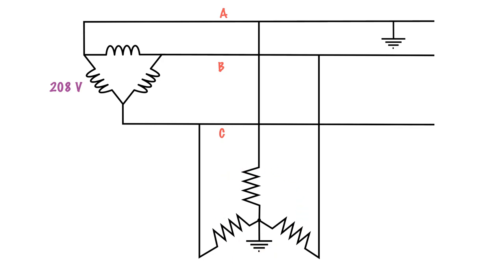With A line being grounded, this is ground, which is the same potential as ground here. So we have a ground fault up top, we have a ground at our point here, which means that this point and this point are the same potential, which means that this point over here and this point over here are at the same potential. So if that is true, then I have no potential difference across my light bulb. If I have no potential difference across my light bulb, then the light is not on. So this light bulb in a ground fault situation will go out.